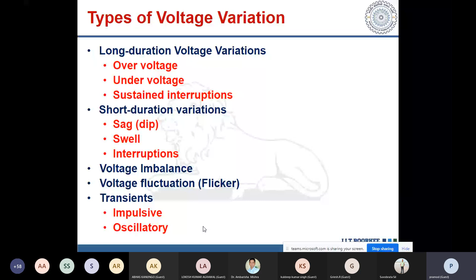If there is an over voltage, there will be over stress on insulation, and the life of the cable, your capacitor, etc., will deteriorate. Under voltage means more current will be drawn by the motor to have the same power, that increases the heat, that reduces the life of the machine.